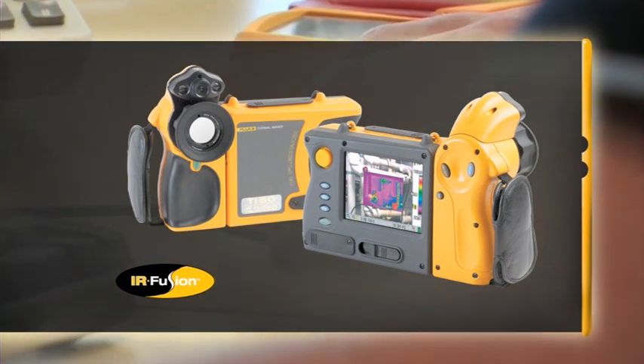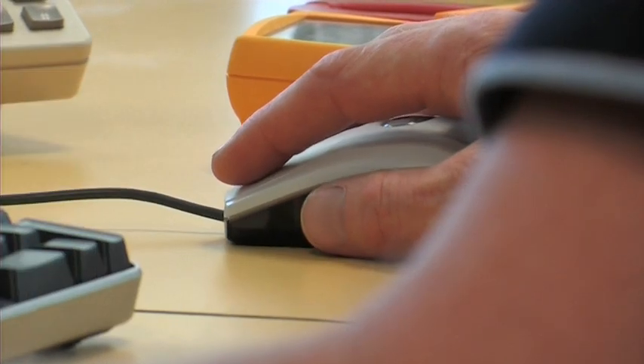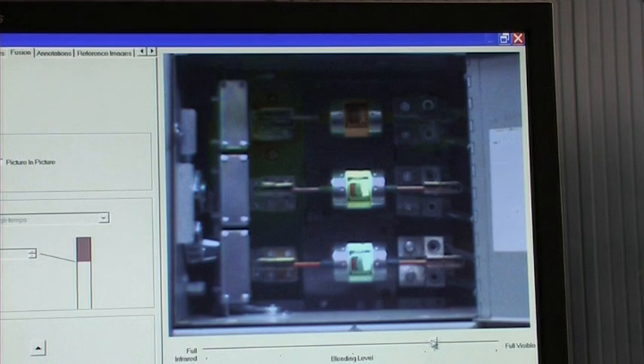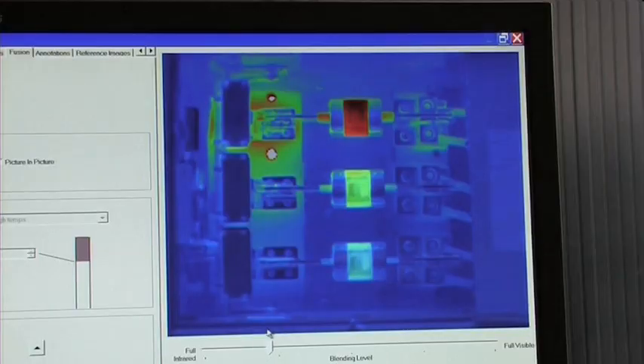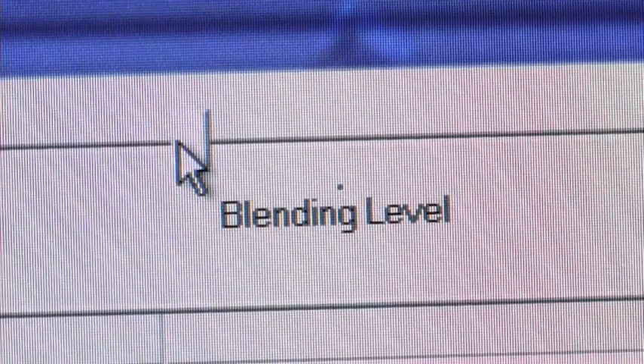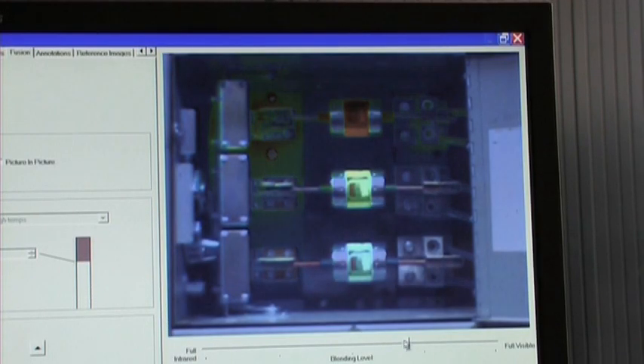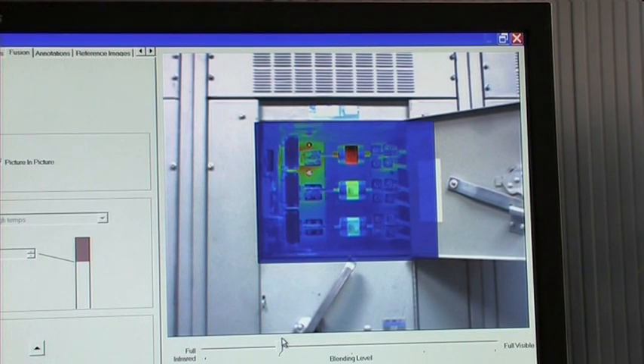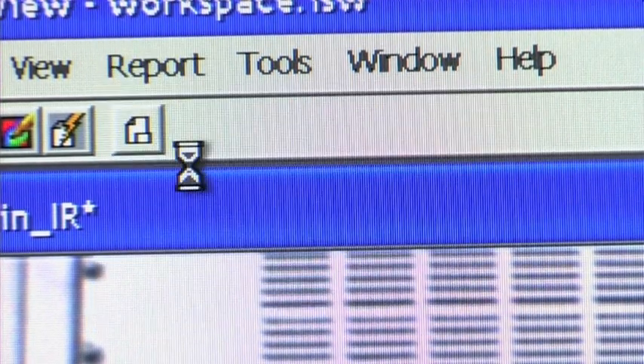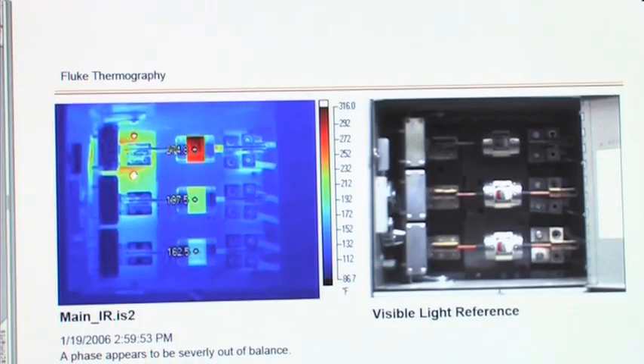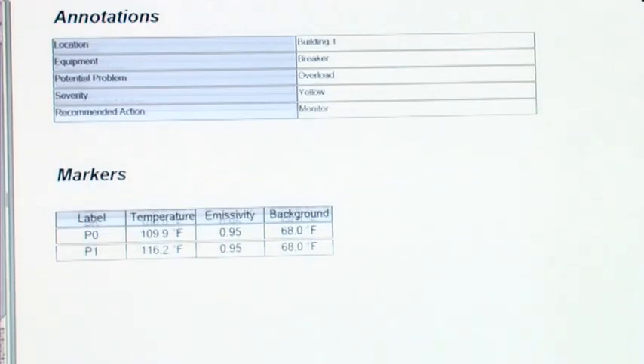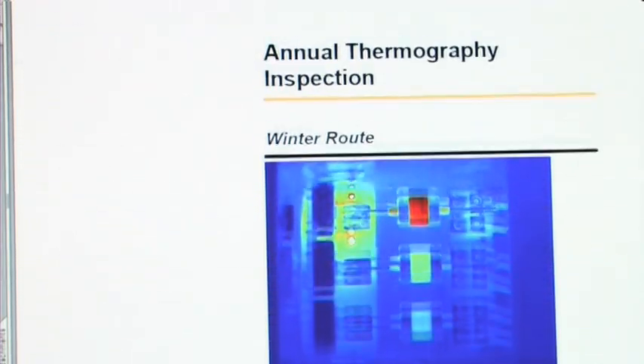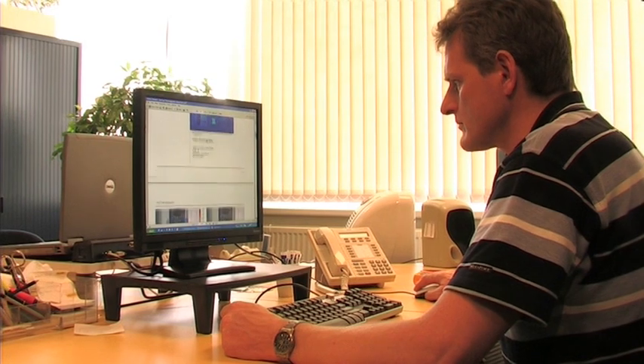Fluke IR FlexCams take thermal imaging a step further with IR Fusion technology. Fusion links a real-world visual image with a thermal image. It merges the two images into one, with the possibility to blend between the two images or create picture-in-picture combinations. Both the visual images and thermal images are available for use in reports. This will speed up documentation by reducing the need to look for individual images taken with a separate digital camera. IR Fusion helps to better identify and report suspect components to enable the repair to be done right the first time.